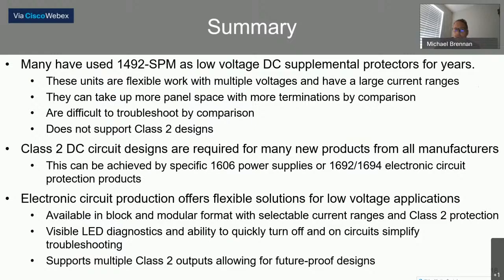So one of the things that you want to take a look at is some of the sensors and safety devices that you're using, to make sure that they don't require Class 2. And if they do, applications like this can make it easy for you to implement. So understand if you do see a requirement for a Class 2 circuit design, it can be achieved specifically with 1606 power supplies or these electronic circuit protection devices.